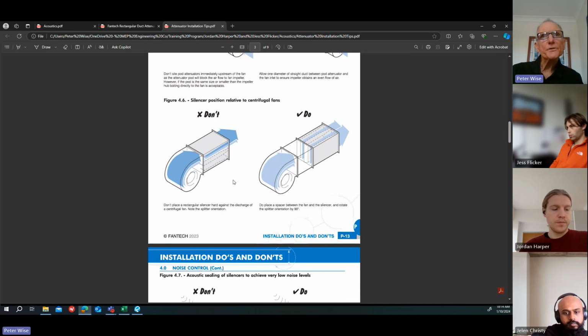Silencer position relative to centrifugal fans. So with a centrifugal fan, the air's going around and spinning out the top. This is showing horizontal splitters. Obviously, the air is being forced to the top of the duct, so most of the attenuator doesn't even get to see the air. So you're going to have a very high pressure drop. You're going to try and force the air through one passageway. You get regenerated noise. It's just not going to work. What they are suggesting you do is put a spacer piece of duct in before the attenuator and turn the splitters vertical so that the air's got a chance to pass through the whole attenuator, not just a part of it.